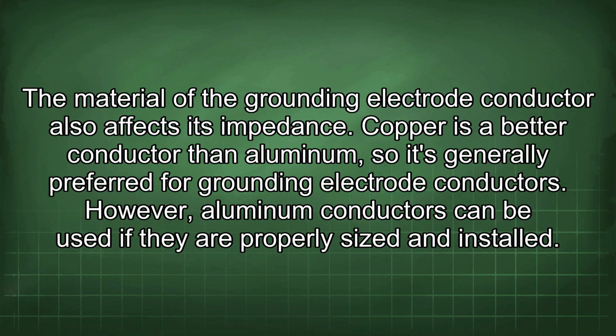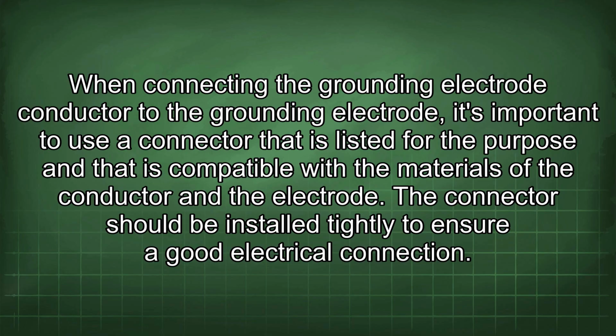The material of the grounding electrode conductor also affects its impedance. Copper is a better conductor than aluminum, so it's generally preferred for grounding electrode conductors. However, aluminum conductors can be used if they are properly sized and installed. When connecting the grounding electrode conductor to the grounding electrode, it's important to use a connector that is listed for the purpose and that is compatible with the materials of the conductor and the electrode. The connector should be installed tightly to ensure a good electrical connection.